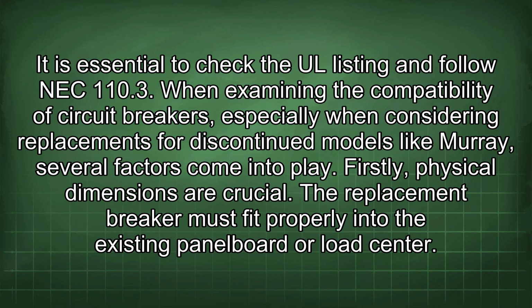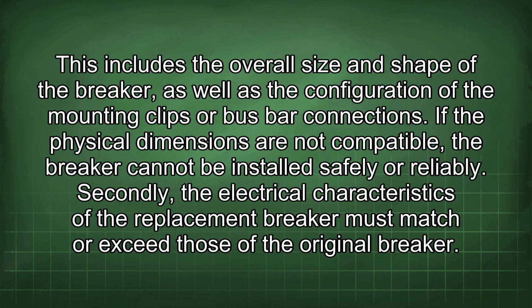When examining the compatibility of circuit breakers, especially when considering replacements for discontinued models like Murray, several factors come into play. Firstly, physical dimensions are crucial. The replacement breaker must fit properly into the existing panel board or load center. This includes the overall size and shape of the breaker, as well as the configuration of the mounting clips or busbar connections. If the physical dimensions are not compatible, the breaker cannot be installed safely or reliably.